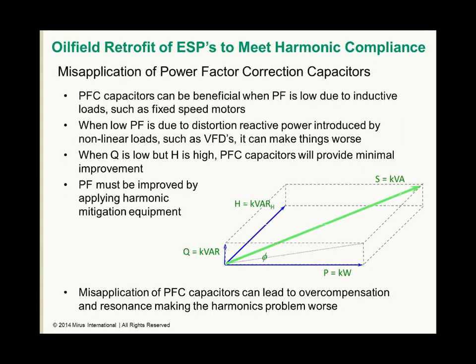I did an earlier webinar on how harmonics have led to 6 power factor misconceptions, which can be found on our website for those interested in investigating this condition further. But I wanted to discuss harmonics and power factor briefly here as well. Harmonic distortion has changed the power relationship from a triangle to a cube. In addition to the inductive and capacitive components, there is a harmonic component, H, that is 90 degrees out of phase with Q and 90 degrees out of phase with the real power, P, in kilowatts. The combination of all 3 vectors is the apparent power S that must be provided.